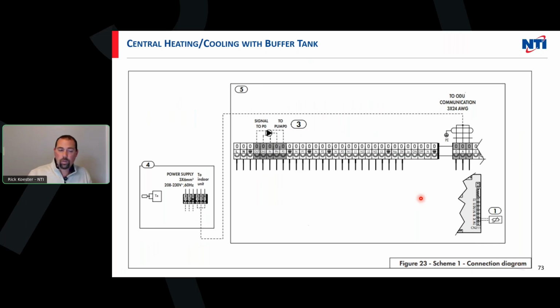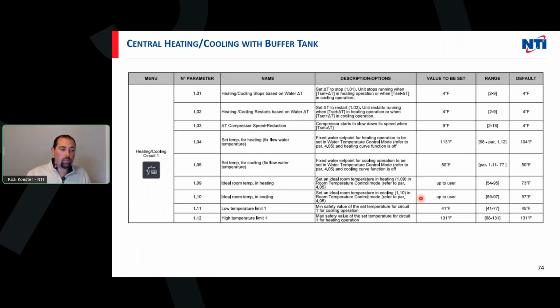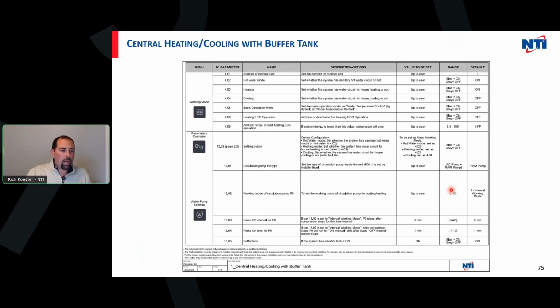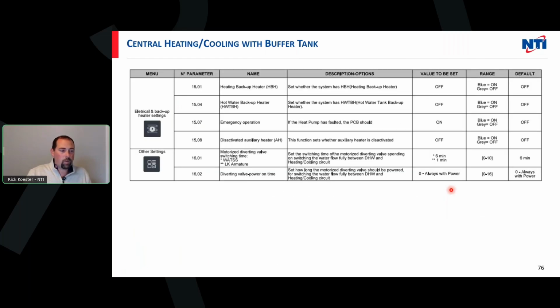Now they can see it from the inputs and outputs of the control box, as well as the outdoor unit terminals. And then finally, we give them the minimum setting parameters that may need to be changed. You'll see here that they have a default, the range they can be adjusted within, as well as the recommended setting. Some of them are labeled up to user, so these will be generated based on the application, and that's something we'll be able to help them with for sure. There are about 2 or 3 pages of them for heating and cooling with a buffer tank.